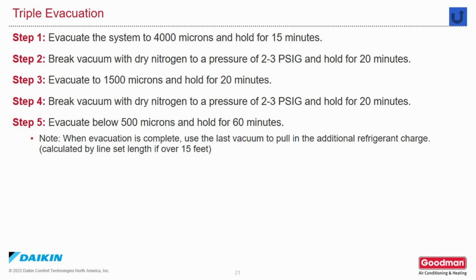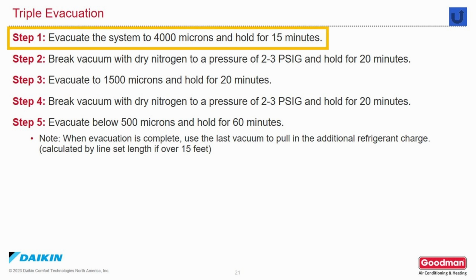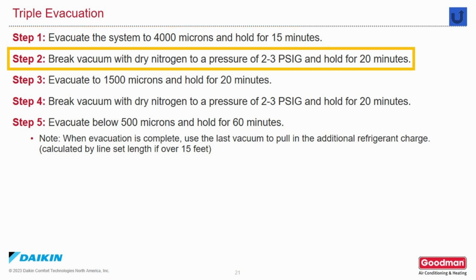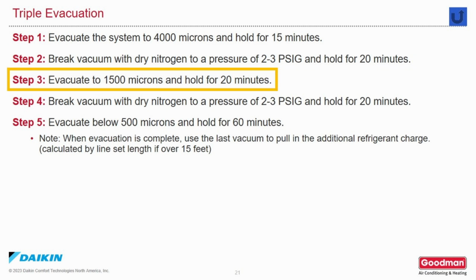Once you are certain that your system is leak-free, perform a triple evacuation. Performing a triple evacuation is the only way to ensure that that line set is dry. Evacuate the system at 4,000 microns and allow it to stay there for 15 minutes. Break that vacuum with dry nitrogen and pressurize it to 2 to 3 psi and allow that to stand for about 20 minutes. Evacuate the second time to 1500 microns and hold that for 20 minutes.